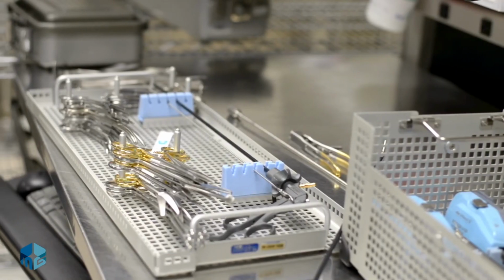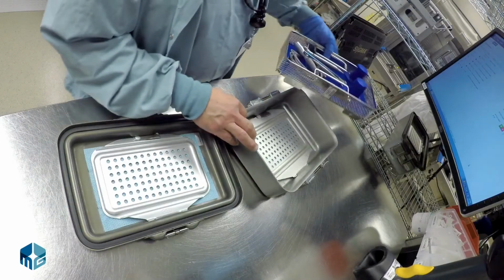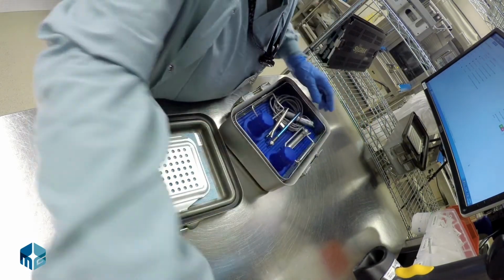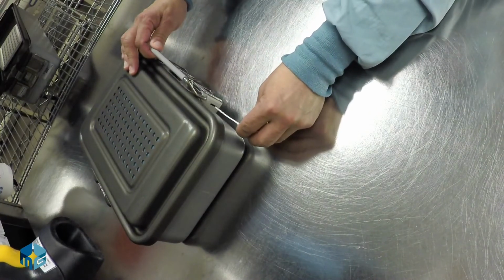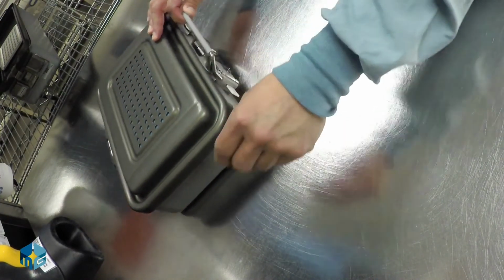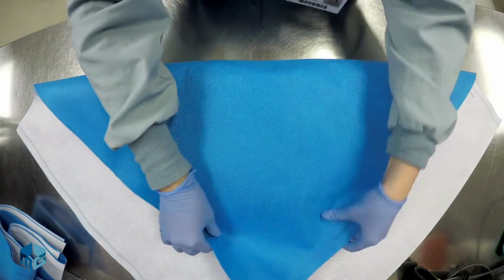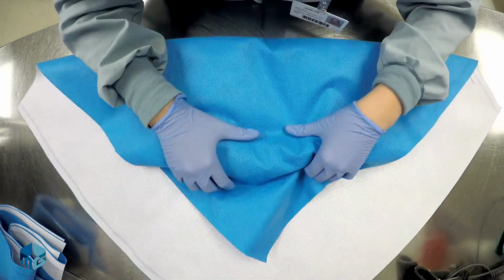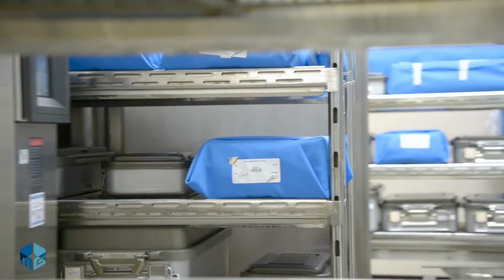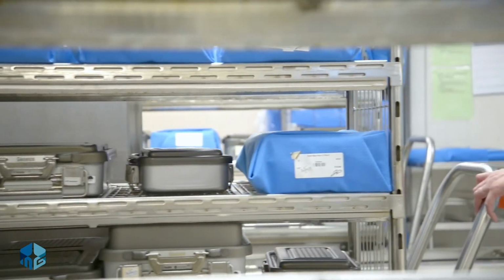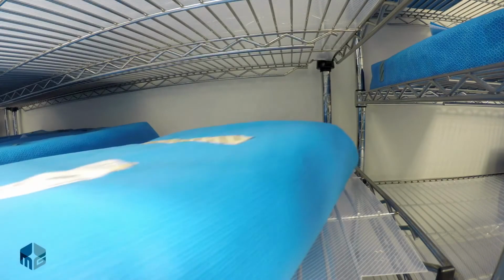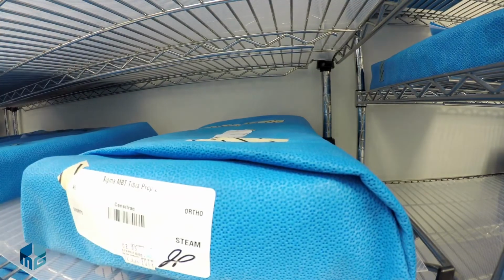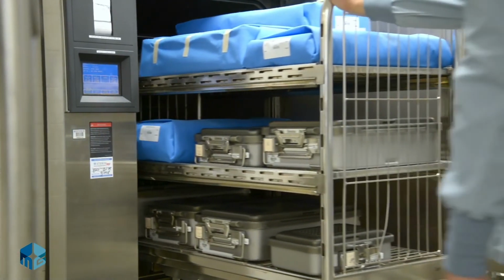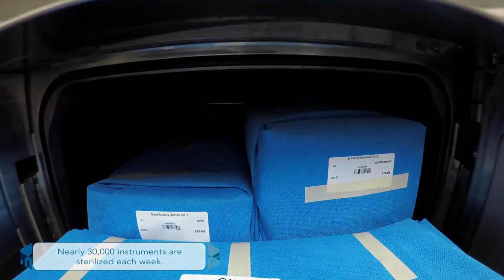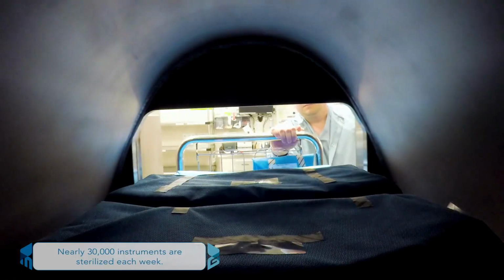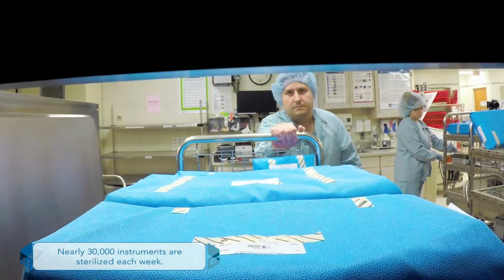We then prepare the instrument set for sterilization by placing all the instruments in a mesh basket. The basket is then placed in a specialized container that is designed for sterilization. Some containers have a sealed hard outer casing, and some must be wrapped with a specialized material called blue wrap. Both types of containers are designed to allow the instruments to be sterilized in the container, and once sterilized, maintain the safety of the instruments while in storage. Sterilization is done by using different methods such as steam, vaporized hydrogen peroxide, and a variety of other methods, but the most common instruments that are used in a surgery are sterilized using steam.